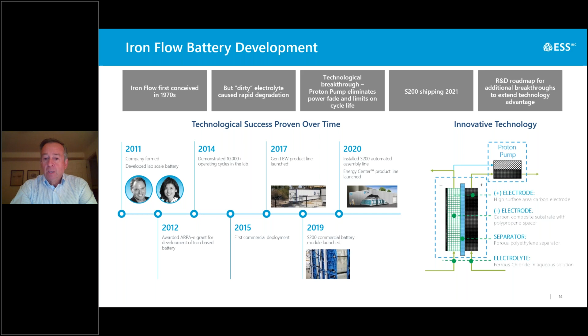Here's a look at what a power module looks like, which is the core element of the iron flow battery. It relies on iron salt water to carry the iron in electrolyte form. When charging the battery, we're electroplating that iron onto the negative electrodes in the battery modules, and when we discharge, we're deplating it back into solution. That proton pump and the innovation around it is what keeps the electrolyte healthy over time.